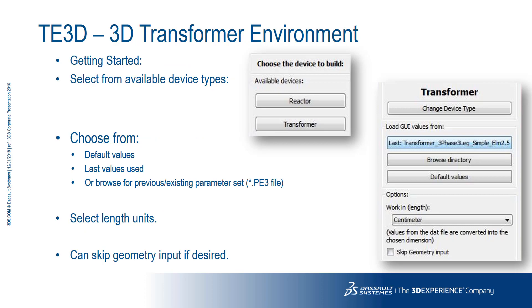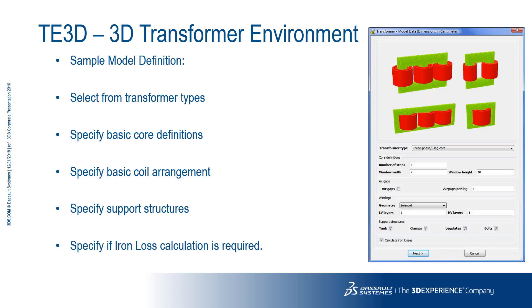The transformer environment is launched from the standard 3D Opera GUI. First you select whether you want a transformer or a reactor. If you've already defined a transformer and want to continue working with it, you have the option to pick up the geometry from an existing file; otherwise, you can generate the geometry afresh automatically. Several standard configurations are available. After selecting one, you can provide basic topological information and choose whether to include details such as air gaps, the tank, clamps, leg plates, and bolts. The more details you add, the greater the number and types of results you can extract, but probably at the cost of more elements and longer run times.